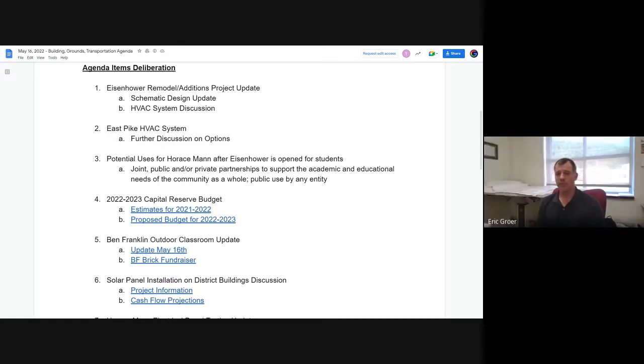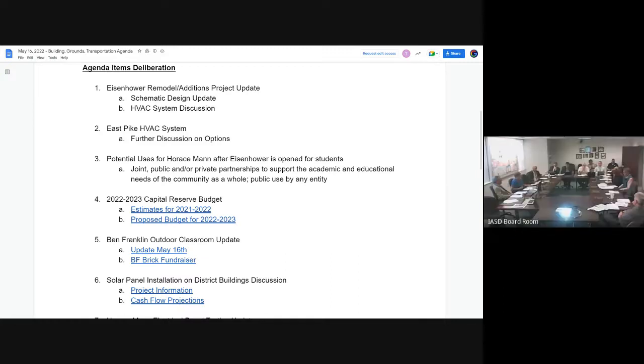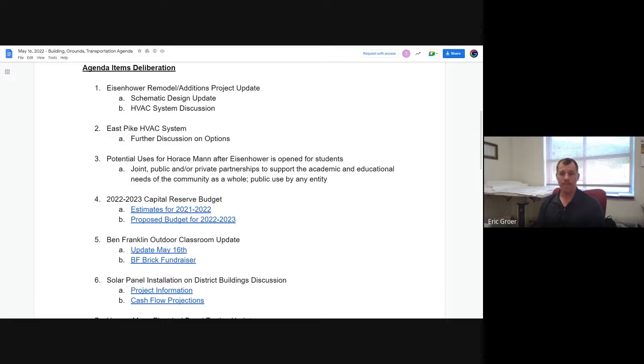Absolutely. If you had a perfectly cubed building that operated year round, you would have a lot less fluctuation in that water. And when you have a lot less fluctuation, you do see the benefits. Those compressors throughout the building run less. But with an unbalanced building like a school, those temperatures are going to fluctuate very low and very high. And when that happens, the compressors in the water source heat pumps are what's going to use all of your energy. That just has to do with an unbalanced load.